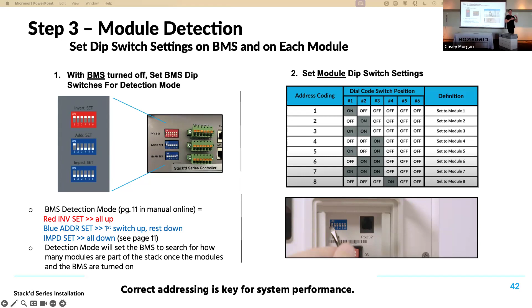Once that's done, you're going to want to adjust the dip switches on the BMS. The BMS has some dip switches here on the side as well. Under this side panel, flip all the red dip switches up—that puts it in detection mode, telling the BMS we're looking for how many modules. Then for the blue dip switches, the first one's up, and the last set are all down. Go to the next slide for me, Casey.